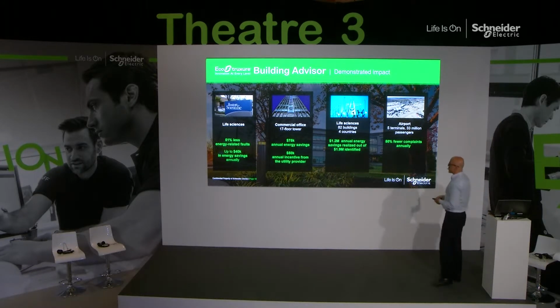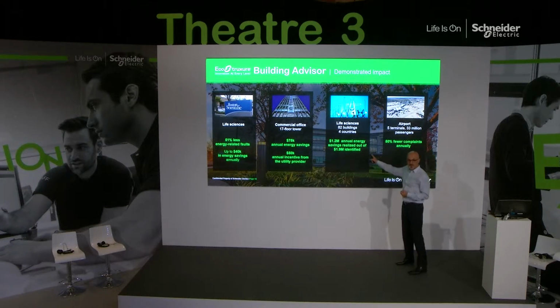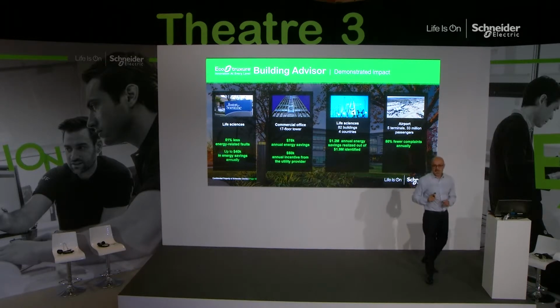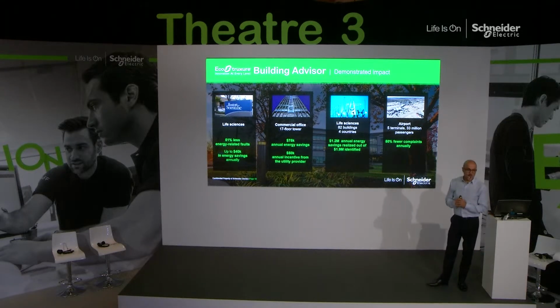The other example is a life sciences building with offices across 4 countries. In one of their offices, we detected a leak in a pipe behind the wall, something there's no way you could normally detect. The system was running fine, everything was okay, the labs were fine, nobody was complaining. The only difference was that the system was working harder than it was supposed to. We detected that by comparing the digital twin to the actual operations, did a root cause analysis, and saved them quite a few dollars.